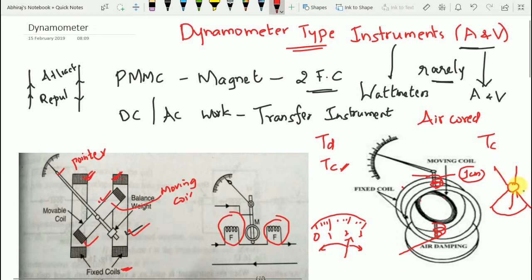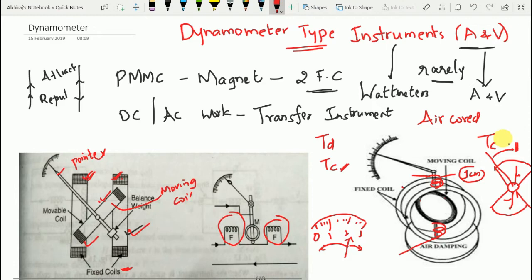The damping torque is provided by air friction damping, using aluminum vanes that move in a sector-shaped chamber. When the pointer deflects, the aluminum vanes also move in the air, and the air provides friction that develops the damping torque. This damping torque halts the pointer at a stable position and exists only when the pointer is in motion. It damps the oscillations so the pointer settles steadily at its correct position.